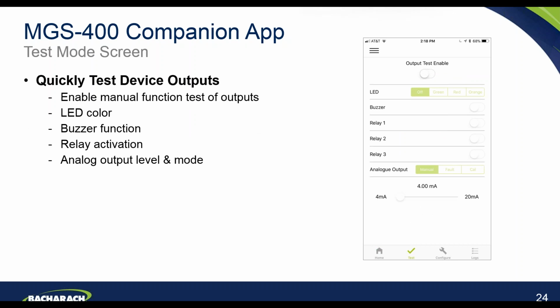The next screen I will show you is the test mode screen. Here you can utilize this screen to quickly test the outputs from the MGS-400 detector. It enables you to manually step through each of those outputs and test them. You can test the LEDs, so you can have them either switched off, green, red, orange. You can test the internal buzzer function. You can test the relay activation, so you can switch the relays on and off, and that will activate any items that are connected to that. You can test the analog outputs, and you can test that across the full range.